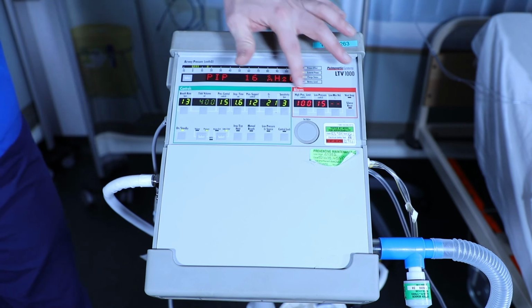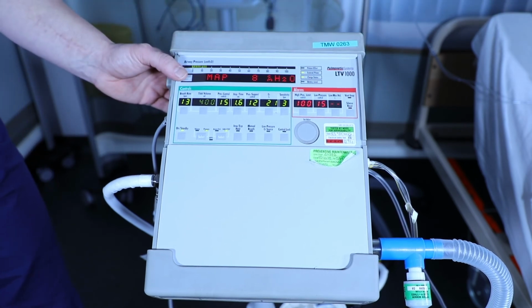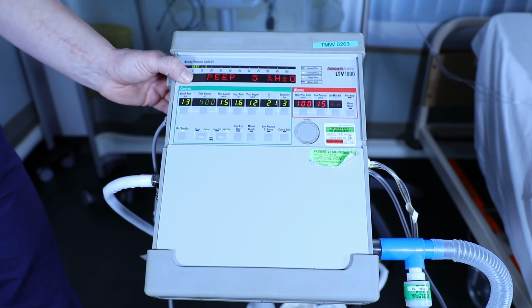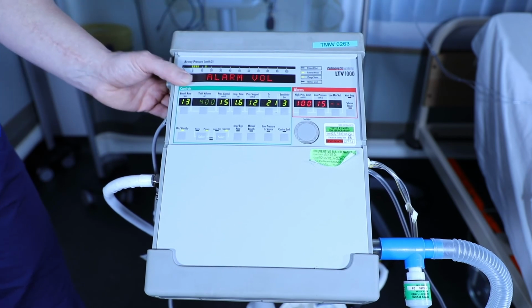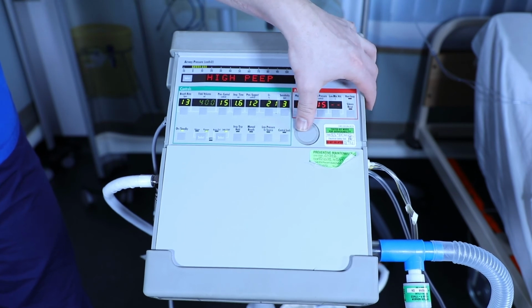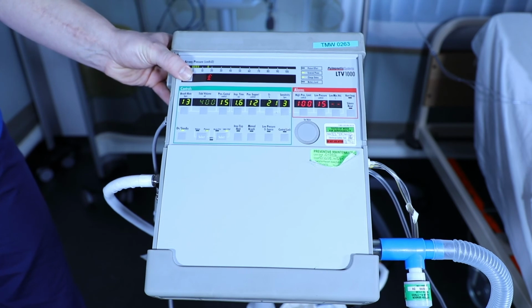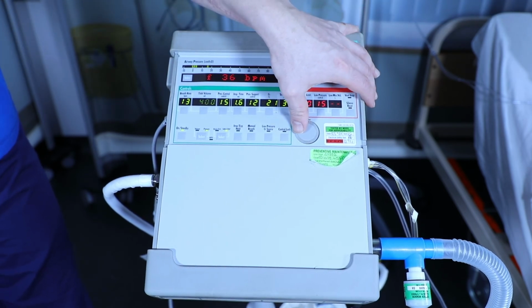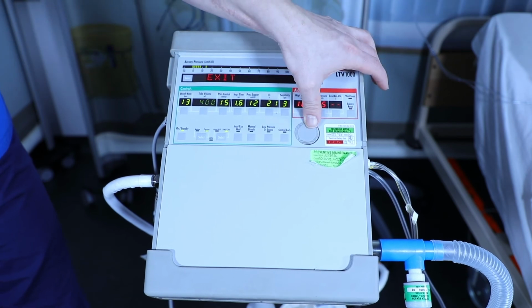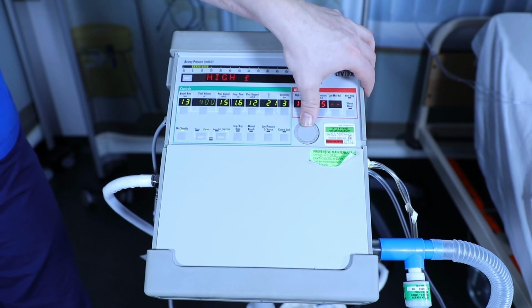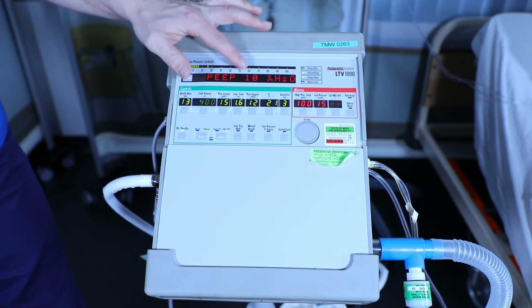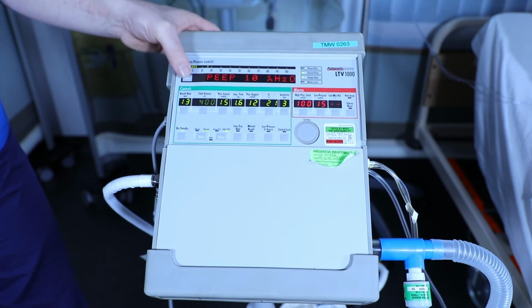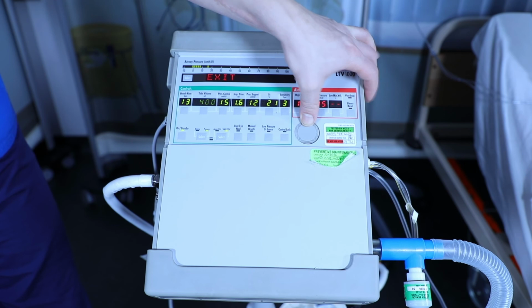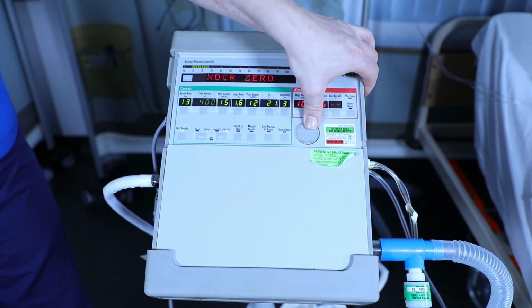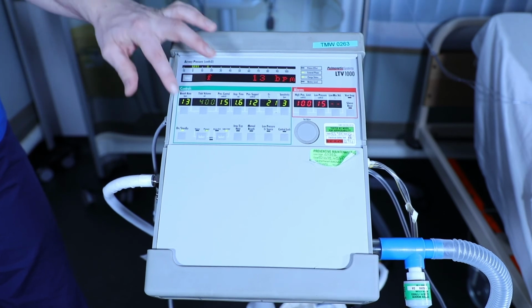As a reminder, as we can see here, we have the 3 external alarms, but to set the PEEP and the respiratory rate alarms, we have to press and hold the select button so that we can enter the extended menu. And once that appears, we now select for the alarm option, and we scroll round until we see high frequency. If we select this now, we can select frequency and change this accordingly. We then scroll to the high PEEP, press select, and we can see it's currently set at 10, but we can change this by using the jog dial. Once we're finished with this, we press exit and again to return to the ventilation mode.